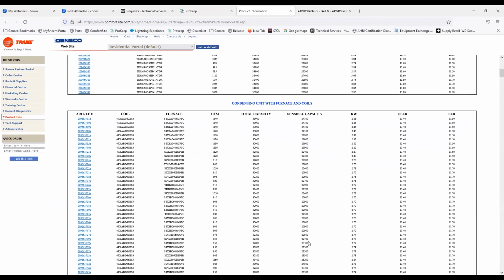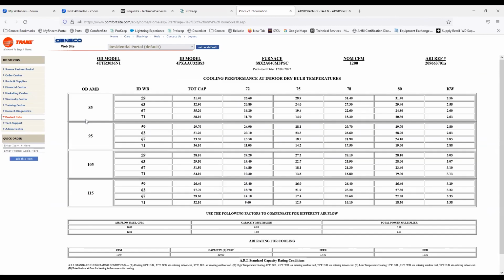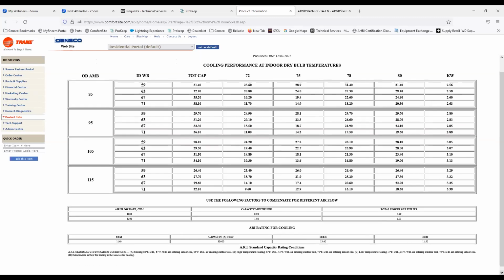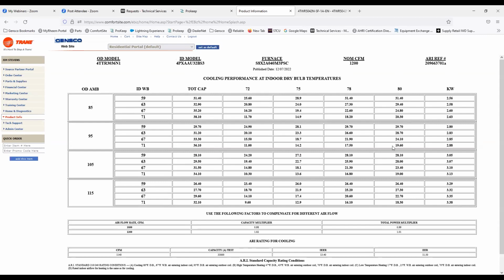And then once you find it, you go to the AHRI reference number and you can click on that AHRI reference and there's your expanded rating right there. Okay. Those are capacities with temperatures, capacity multipliers for the airflows. Tells you what they set the airflow for when they did the test. So they got all that information right in there.